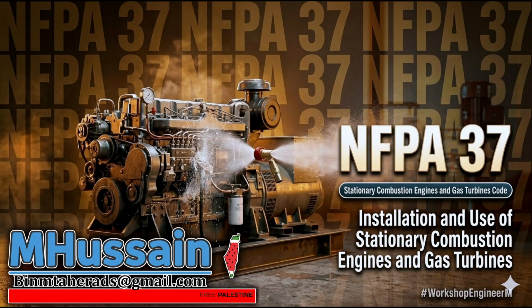Right. Through a process called pyrolysis, the heat conducts into the wood, dries it out completely, and eventually it just bursts into flames. So you can't just punch a hole in the roof and run the pipe out. Absolutely not. NFPA 37 requires ventilated metal thimbles for any penetration through combustible assemblies. A thimble, like a sleeve around the pipe. Yes, a double-walled metal sleeve. It creates an air gap between the hot exhaust pipe and the structure. Air is actually a fantastic thermal insulator.